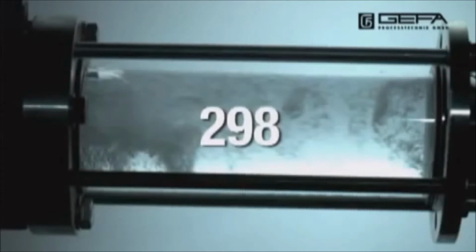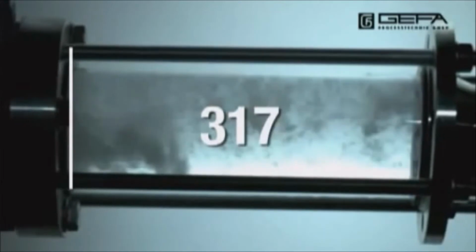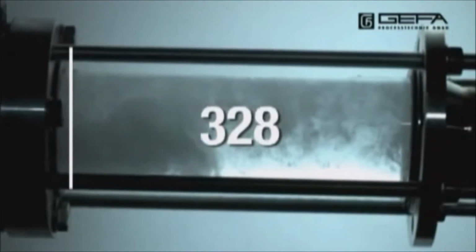Consequences of the water hammer effect. In slow motion you see how water spray squirts out of the flange gasket area. The studs are stretched and at the same time the whole construction is spoiled with a deflection of 15 mm.